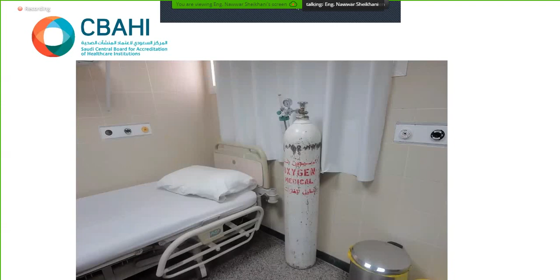Compressed gas, just a sample we found in a hospital, actually a remote area hospital, where you can notice the outlet of medical gas, but they have this, I don't know whether it's backup or not, freestanding, and here the storage is absolutely wrong. It could fall down over the patient. Plus, I would like to mention that the bed location is wrong here. As engineers and clinical staff, we should consider that the clearance around the bed should be 1.2 meters, 120 centimeters, and the head should be 35 centimeters away from the wall. Why? This is to ease the work and the maneuver of the crash cart and ease the duty of the CPR team, if needed.